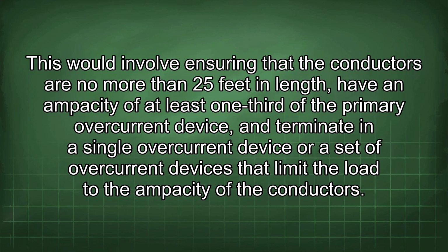This would involve ensuring that the conductors are no more than 25 feet in length, have an ampacity of at least one-third of the primary overcurrent device, and terminate in a single overcurrent device or a set of overcurrent devices that limit the load to the ampacity of the conductors.